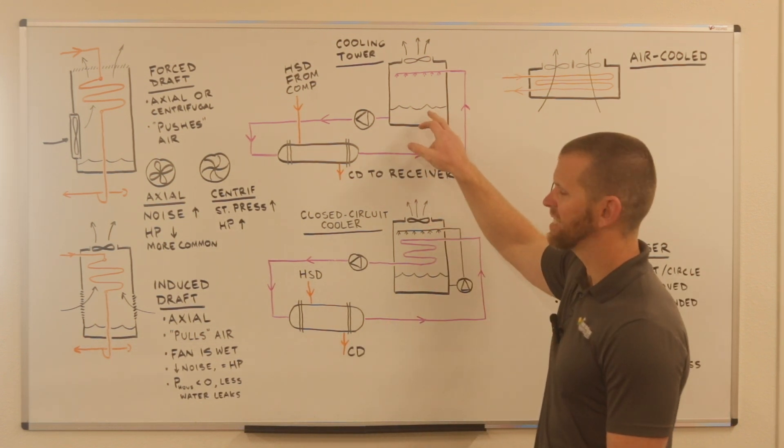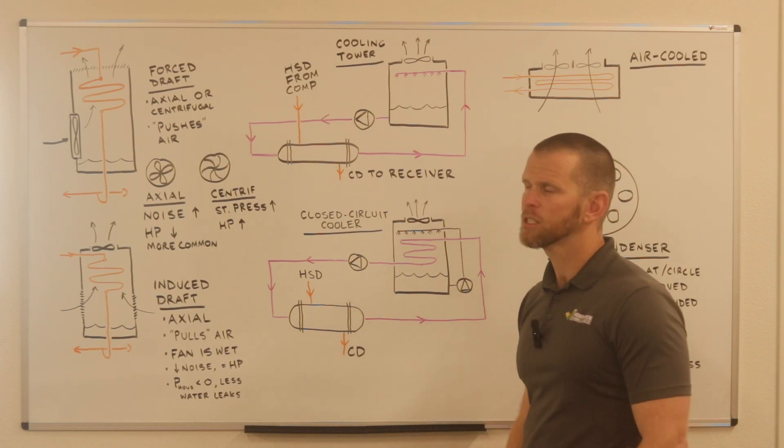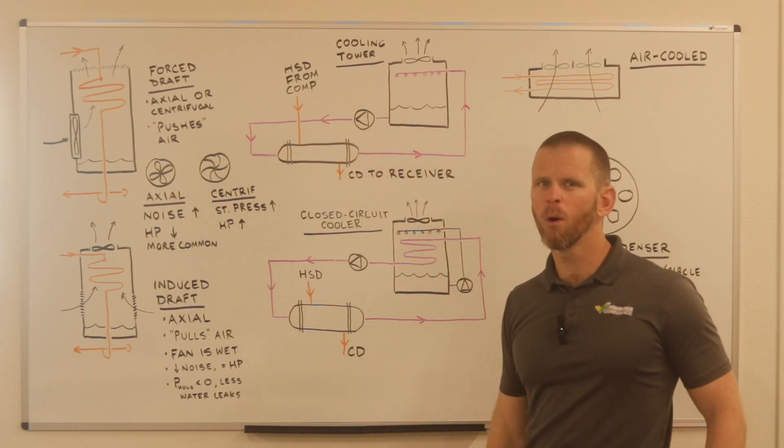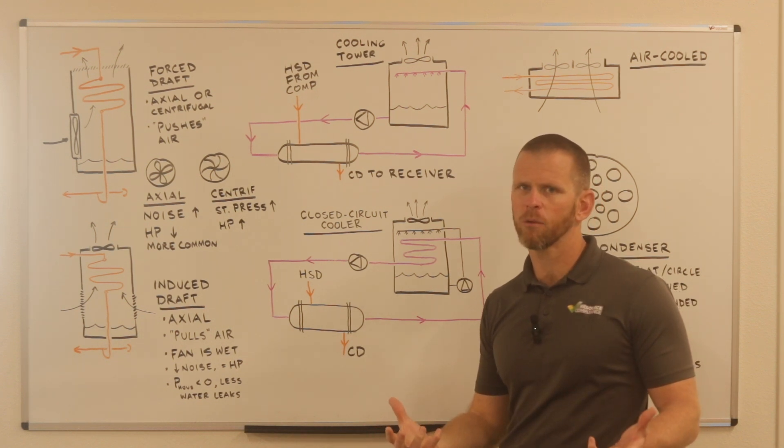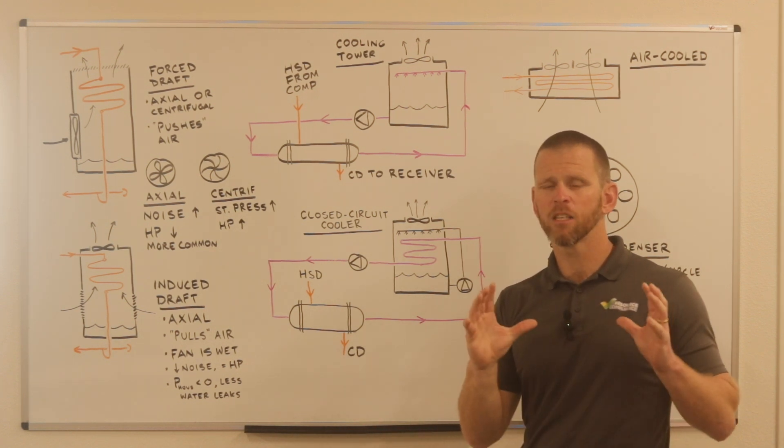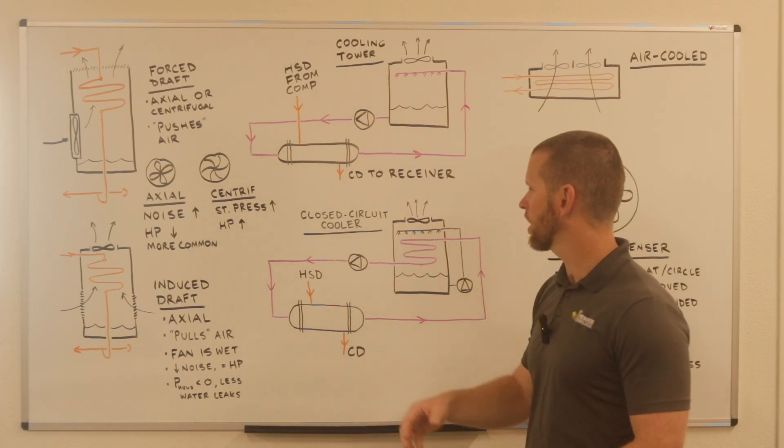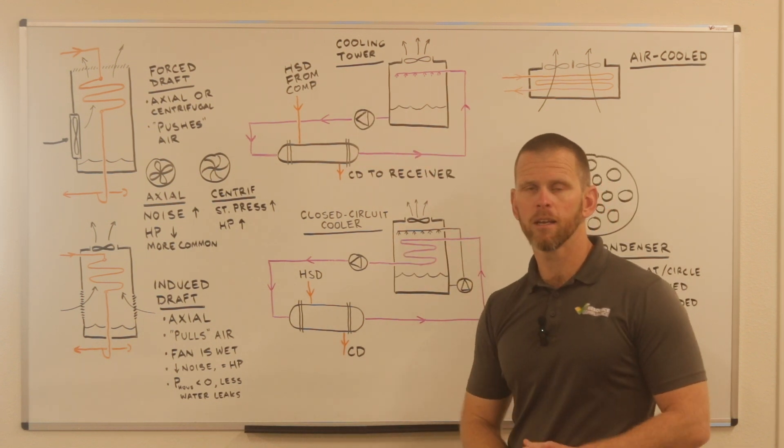Furthermore, the water in both of these needs to be treated chemically. By cycling, by using that same water for both purposes, it creates challenges in that regard as well. But that provides the overview that you need to understand the difference between a cooling tower and a closed circuit cooler when it comes to fluid cooling condensers.